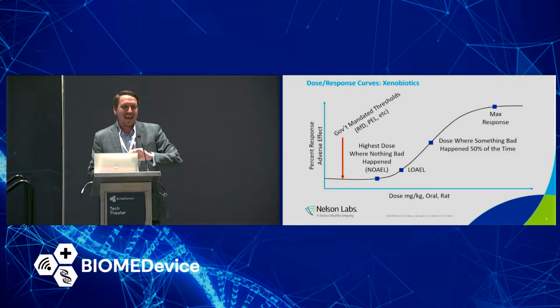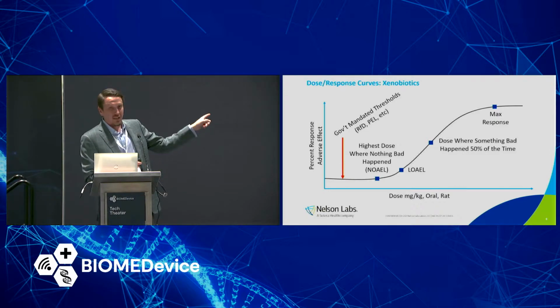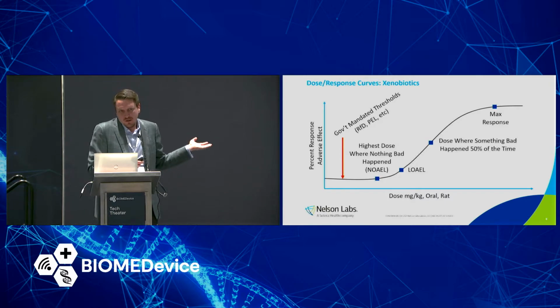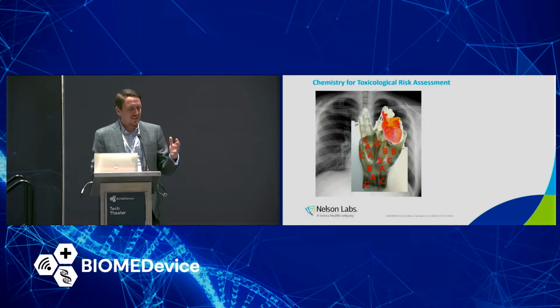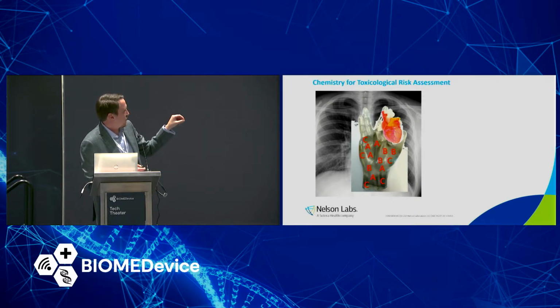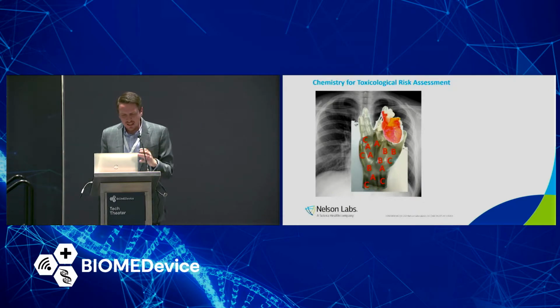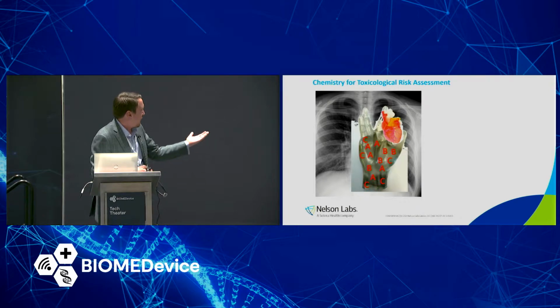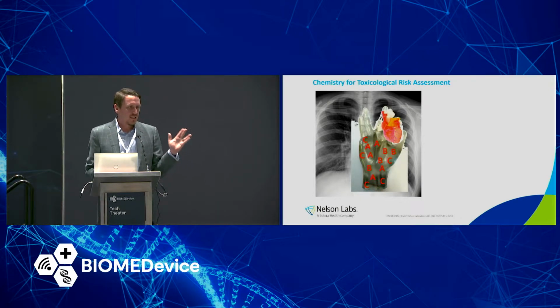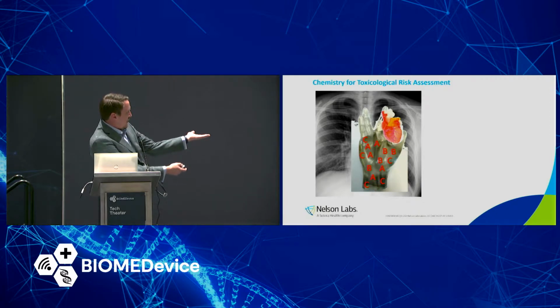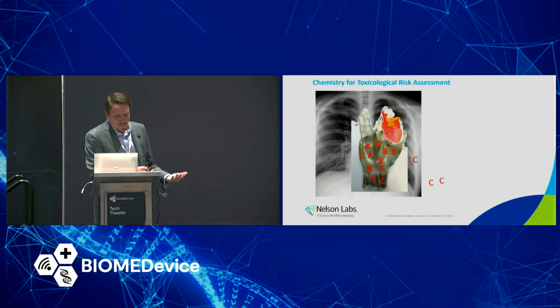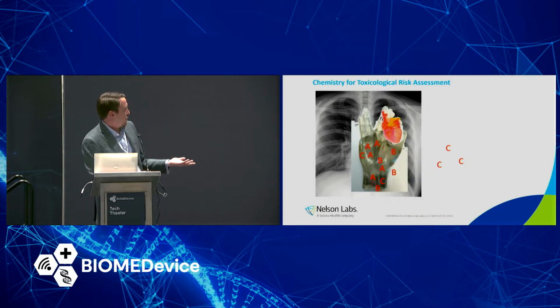So we want to be able to find anything that might leave the device and also measure it with enough accuracy and low enough that we can compare it to all of these curves. Yeah, it's tricky. And so the way that we do that, I want to explain the terminology, extractables and leachables, just a little bit. So the notion is, if this device is in the body, so this is a real device, it's a 3D printed Spock hand. It's designed to be implanted in the body next to the heart so you can keep the memory of Leonard Nimoy with you always. If you are the Trekkie that gets this implanted, after it's implanted, compounds will slowly leave, and those are the ones that we really want to measure.